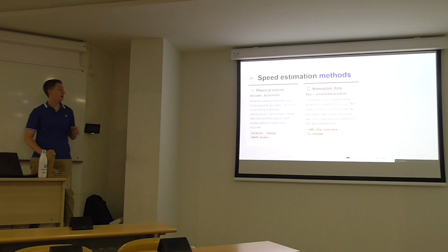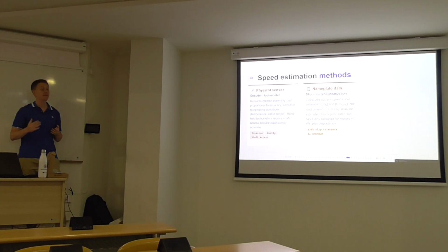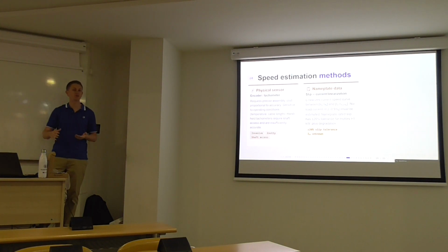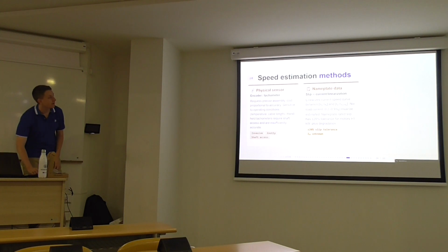And also, apart from that, the nameplate rated slip has a tolerance of ±20% in motors above 1 kilowatt. And also, you always have some degradation in the motor. So it's very unreliable to estimate the speed based on nameplate data. So I do not recommend doing that ever, okay?